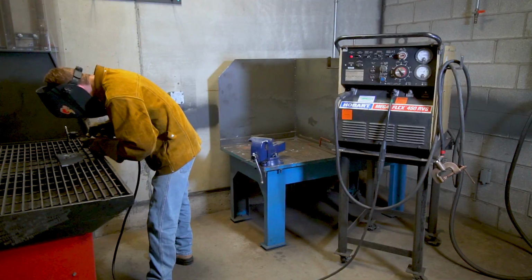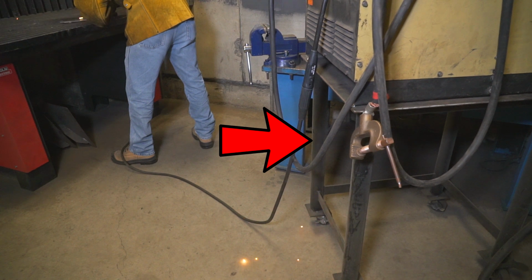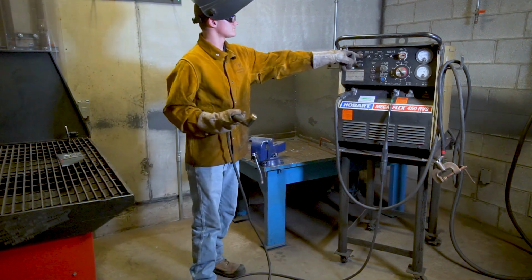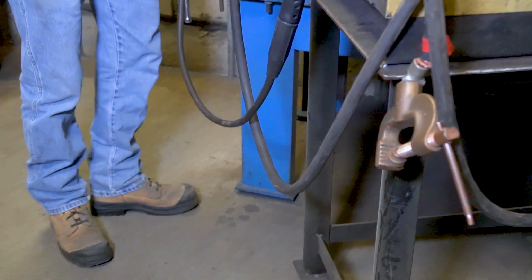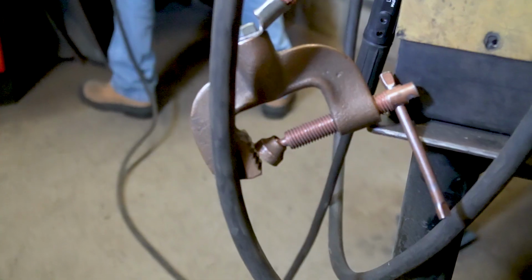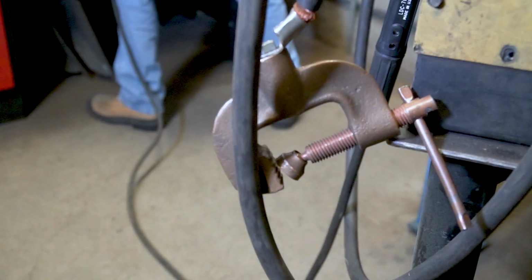Now we will repeat the welding operation after the welder has made the simple mistake of forgetting to connect the work lead to a point close to the welding area. As you can see here, the bare current return clamp has been left in contact with the machine chassis through the cart that it is sitting on.